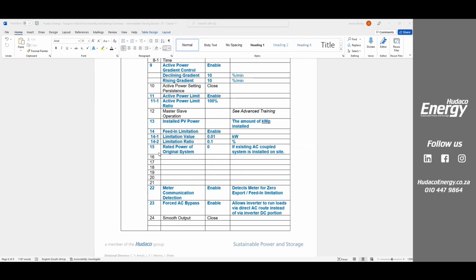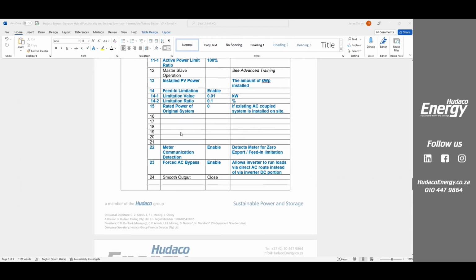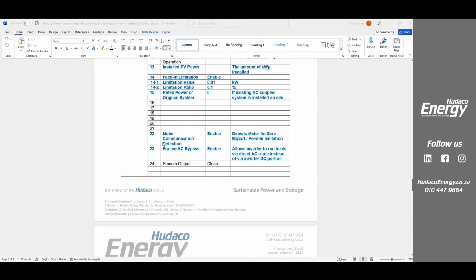If it's your PV that you're putting on the roof and you're plugging straight into the hybrid, this stays at 0 and you put it in your installed PV power there. So this installed PV power is the power that's feeding into the MPPTs on the inverter. This here is if there's an AC coupled system. Okay. The rest of these are not applicable for today.